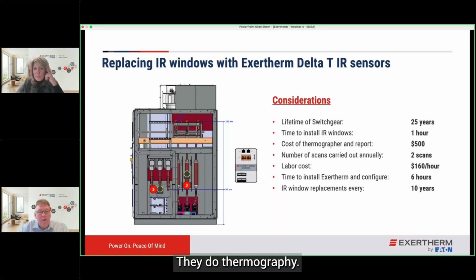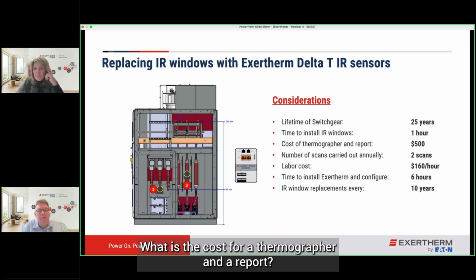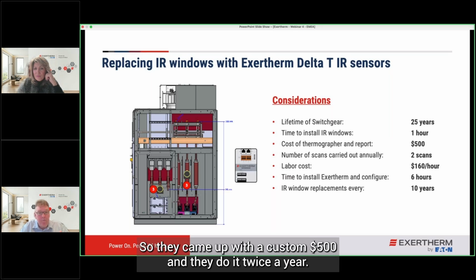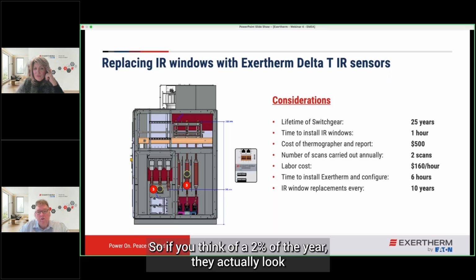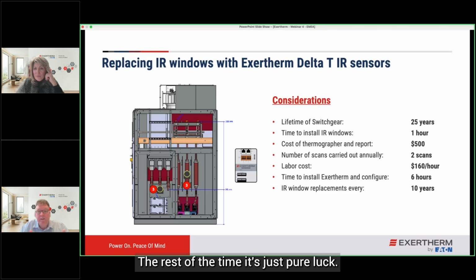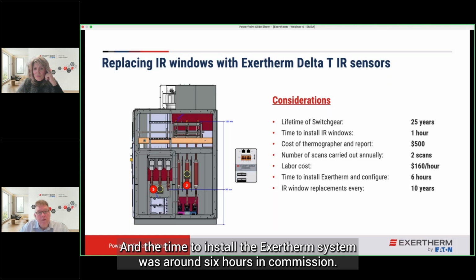They do thermography. What does it cost for a thermographer and the report? They came up with $500, and they do it twice a year. So if you think of it, 2% of the year they're actually looking to see what's happening. The rest of the time, it's just pure luck.